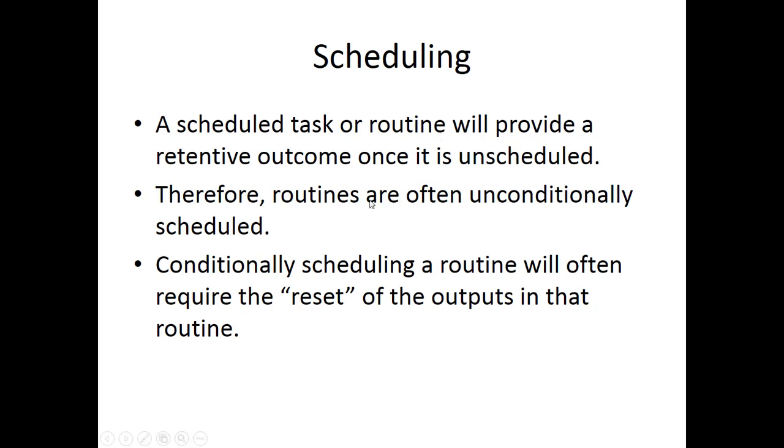Therefore, routines are often unconditionally scheduled. And if you do conditionally schedule them, you're going to need some way to reset the output back in the main routine, or else it's going to stay on.